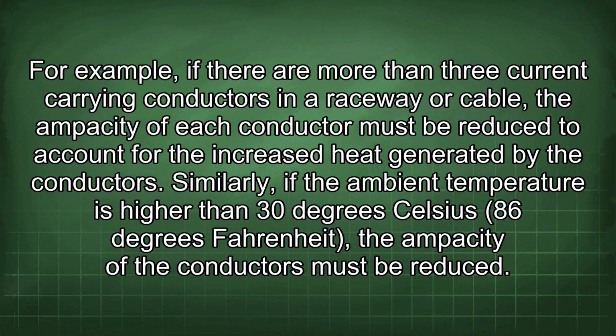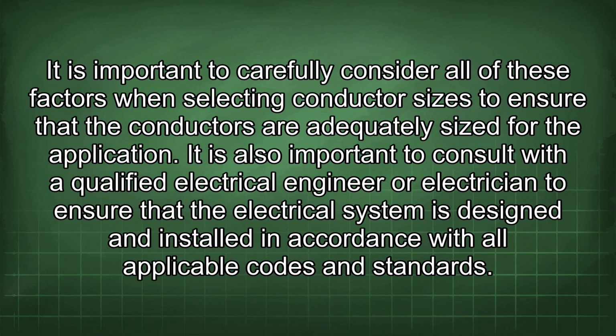Similarly, if the ambient temperature is higher than 30 degrees Celsius (86 degrees Fahrenheit), the ampacity of the conductors must be reduced. It is important to carefully consider all of these factors when selecting conductor sizes to ensure that the conductors are adequately sized for the application. It is also important to consult with a qualified electrical engineer or electrician to ensure that the electrical system is designed and installed in accordance with all applicable codes and standards.